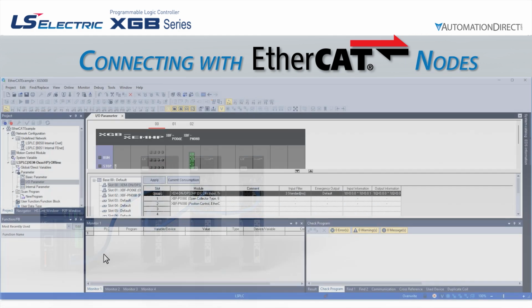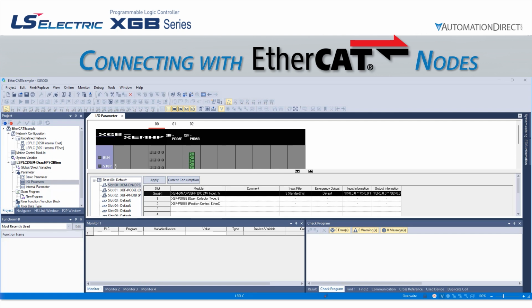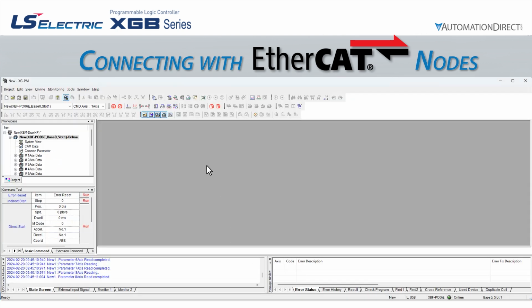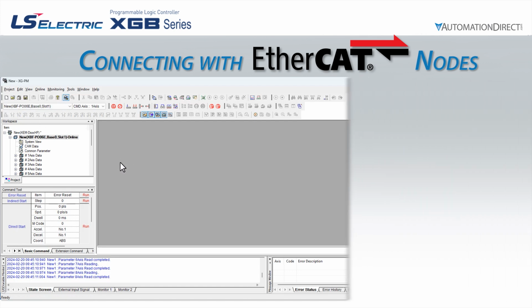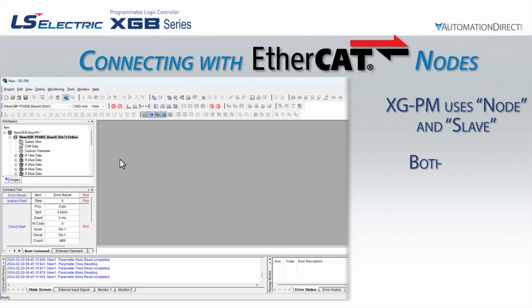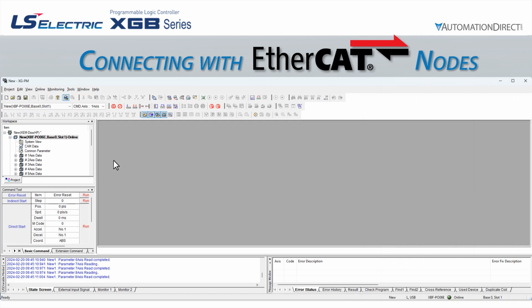We have XG5000 and XGPM open and have already read the blank project out of the PN08B EtherCAT module connected to our CPU. It's also important to note that the software uses node and slave interchangeably. They both refer to the devices on the EtherCAT network that are not the master. To start our configuration, let's have our master grab the configuration information from the EtherCAT nodes on the network.